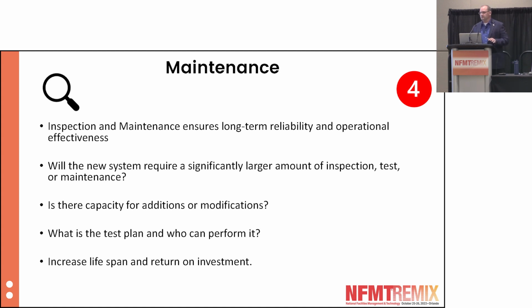They installed 2,196 spot smoke detectors to replace those 120 air sampling systems. It was supposedly cheaper, but now what do you as a facility manager have to do every year to those 2,196 smoke detectors? You have to test each and every one of them, whereas with the sampling systems you'd only have had to test one sampling port per detector, out of 120 detectors.